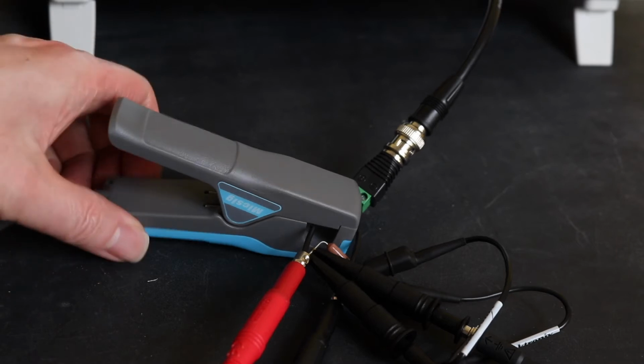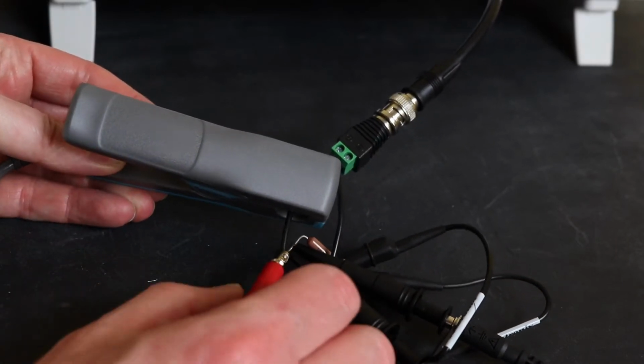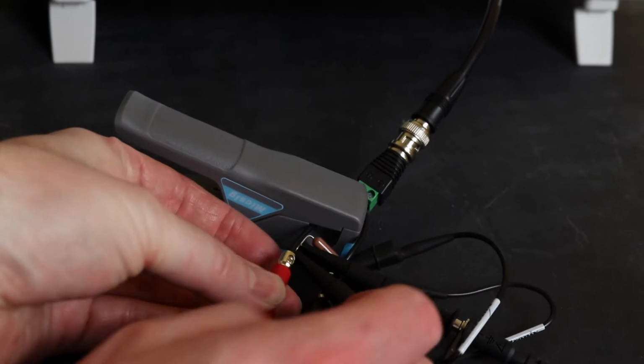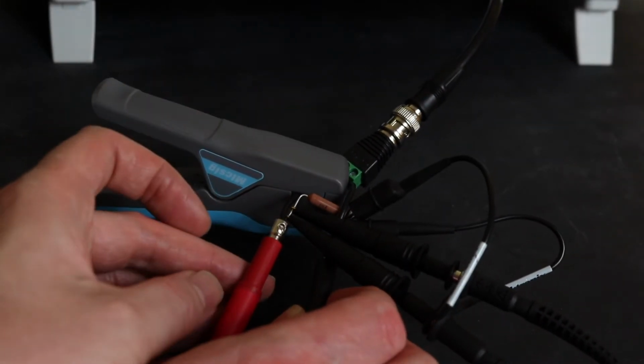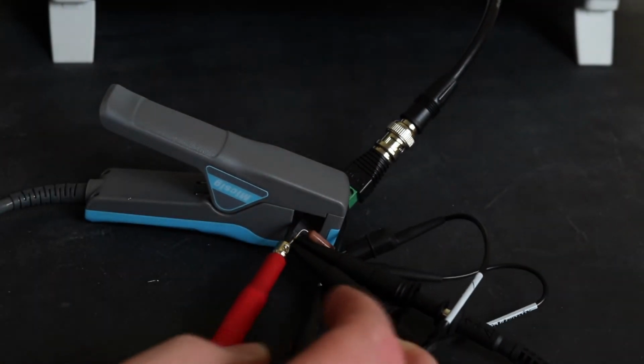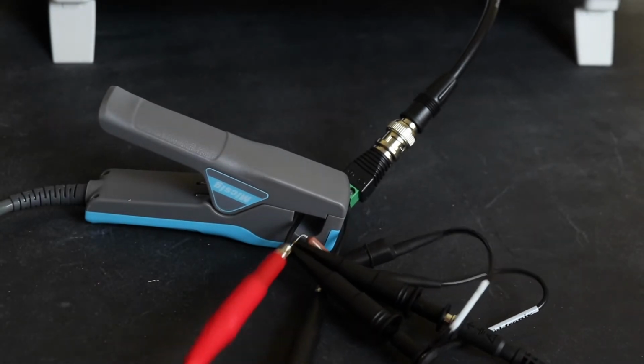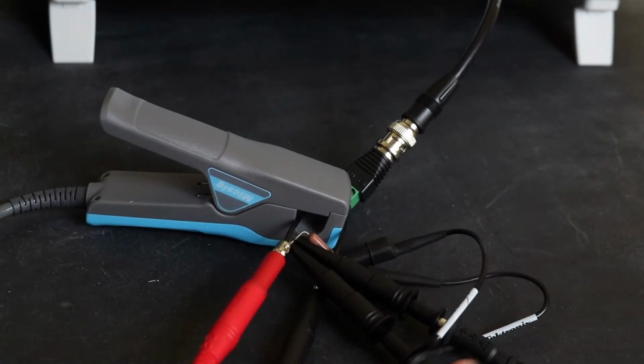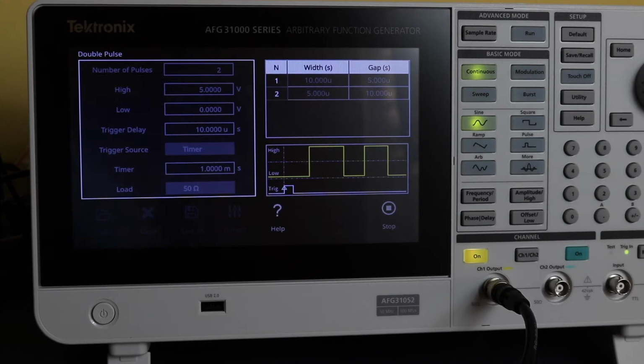Over here you can see the other half of the current clamp wrapped around a wire, and then I've got a 50 ohm resistor across the output of the AFG31052. This goes to the differential probe, and then channels 1 and 2 are on the normal oscilloscope probes. Looking at the AFG31052, all I've done is set up the double pulse software to put out a couple of pulses on a 5 volt peak waveform into a 50 ohm load, and then I'll look at the edge of them using the oscilloscope.